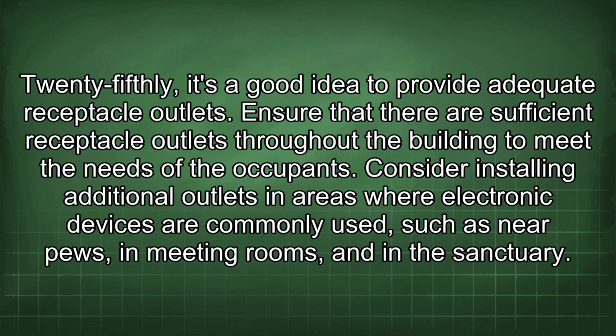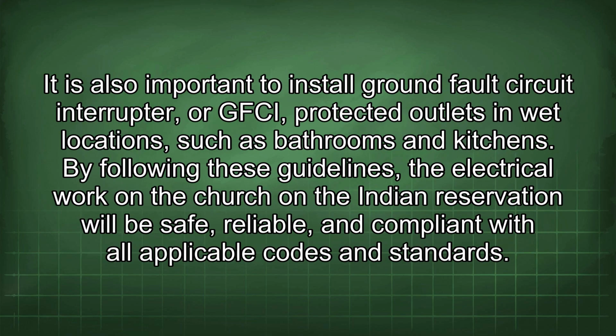25thly, it's a good idea to provide adequate receptacle outlets. Ensure that there are sufficient receptacle outlets throughout the building to meet the needs of the occupants. Consider installing additional outlets in areas where electronic devices are commonly used, such as near pews, in meeting rooms, and in the sanctuary. It is also important to install ground fault circuit interrupter, or GFCI, protected outlets in wet locations such as bathrooms and kitchens.